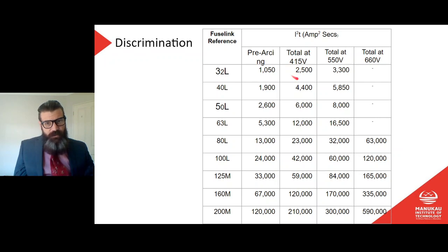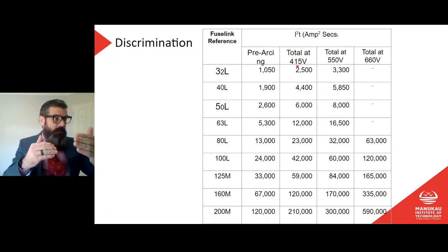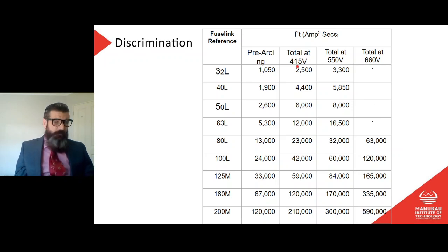So this number here, if we're to get good discrimination, must be less than the pre-arcing number of the next fuse up. So if I had a 32 amp fuse, and I was using it on a three-phase supply, it's going to let through a maximum of 2,500 amp squared seconds. Can I use a 40 amp fuse behind that as backup? No, because by the time this one has blown, this one is starting to blow, and we don't want that. We want this one to not blow if this one can handle it. So this one here, the 50 amp, gives us a pre-arcing of 2,600, and therefore it falls within that. So I could use the 50 amp or anything higher as my next biggest fuse after the 32. Hopefully that makes sense to everybody.